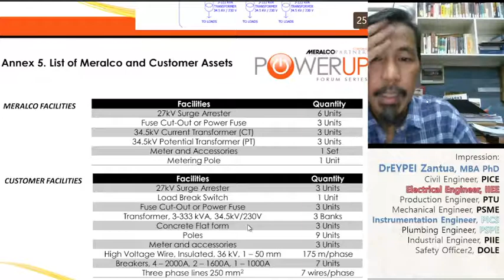Okay. So, concrete platform, 3 units. Poles, 9 units. Meter and accessories. Imagine 9 poles. From one pole of the Meralco, you will have 9 poles because of the 3 transformers, no? Meter accessories, 3 units. High voltage wire, insulated 36 kV, 150 mm, 175 m per phase. Okay? Breakers for 2,000 amperes. Imagine that, no? 1,600 amperes and 1,000 amperes. 7 units total. Okay? So, 3-phase lines, 250 mm squared, 7 wires per phase.